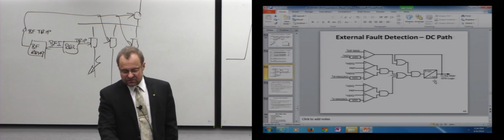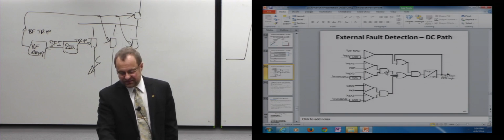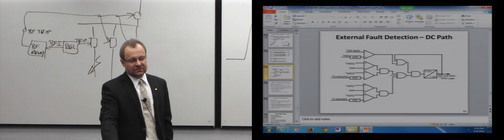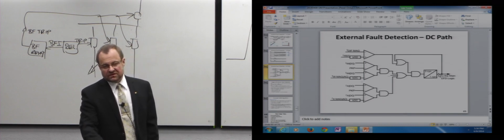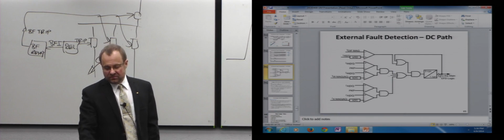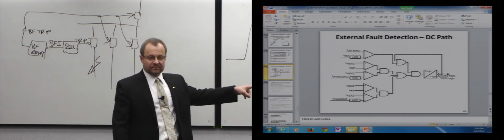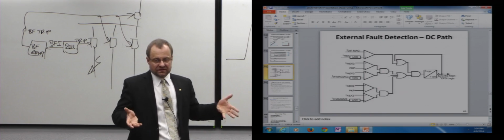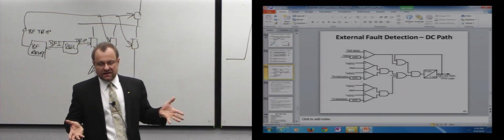Now, there is more to it. I have an interlock here and it basically says this is not an internal fault. So this comparator says differential is below restraining, which means this is not an internal fault. So if this is not an internal fault and I see a DC for 3 cycles, I will say, okay, that's it. If this was an external fault, I got 3 cycles to trip. It's not an internal fault. Let me get ready because those CTs are going to give up. I have a standing DC. I know they don't like DC. I have to get ready.